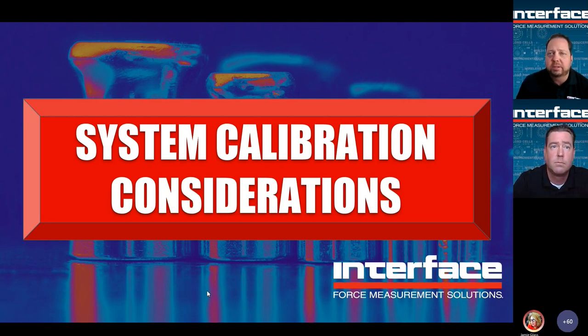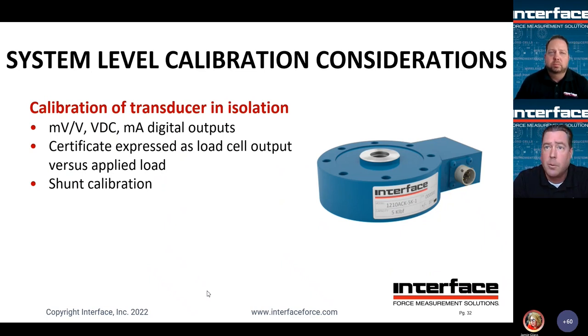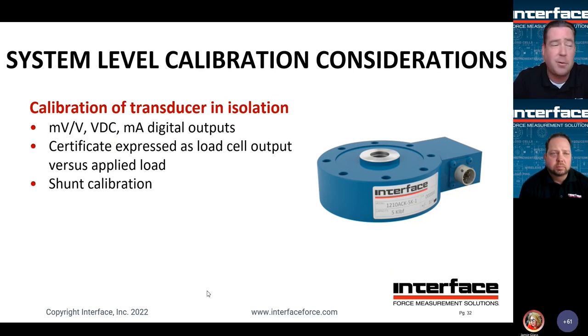All right, system calibration considerations. Elliot, back to you. Thanks, Brian. Oftentimes, it's not just the load cell that comes back for this calibration to define the performance characteristics of each. So let me touch on the different system level or load cell level calibration options that we have. The simplest and most common is a simple calibration of the transducer in isolation, so only the load cell. You can capture outputs from the load cell in millivolts per volt, which would be the standard native output. It could be an amplified load cell, voltage outputs, milliamp outputs, or even digital outputs from the load cell alone. The certificate you would receive would be expressed as load cell output versus applied load. It would also include a shunt calibration, where we apply a shunt resistor across legs of the bridge to provide an essentially simulated output.